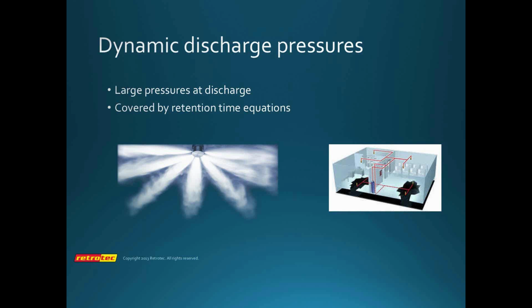What that causes is a situation where we have more agent in the room than we're supposed to. As that agent starts to warm up, it actually expands and supplies the leaks to some degree, which is the reason why we get much higher concentrations and much better retention times of halocarbons than we're supposed to, because we don't actually lose much in the way of gravity losses for the first 3 or 4 minutes, because the agent is expanding continuously.